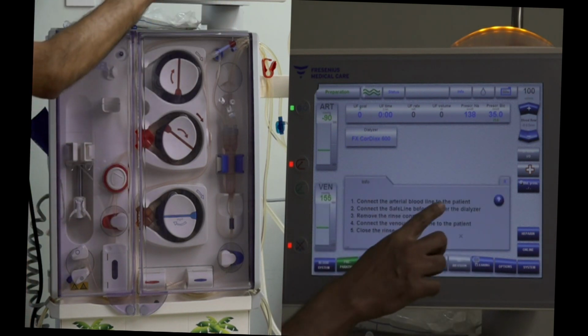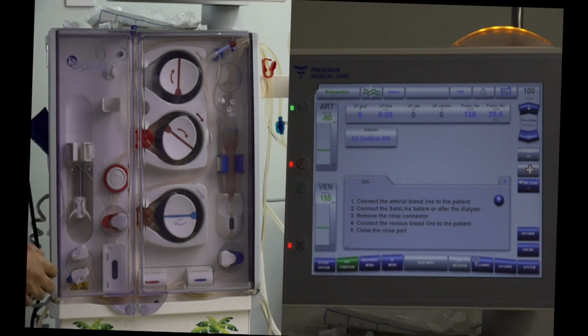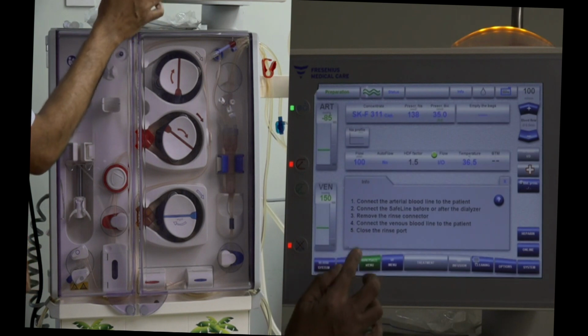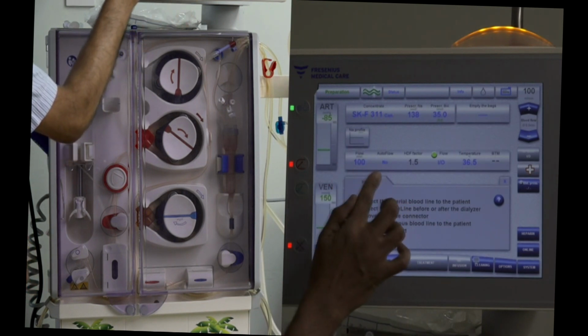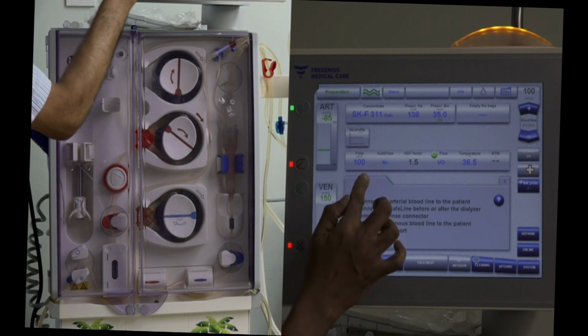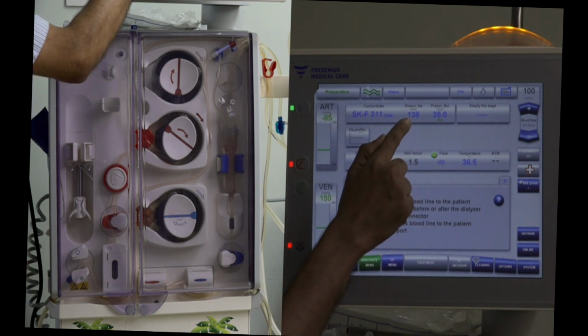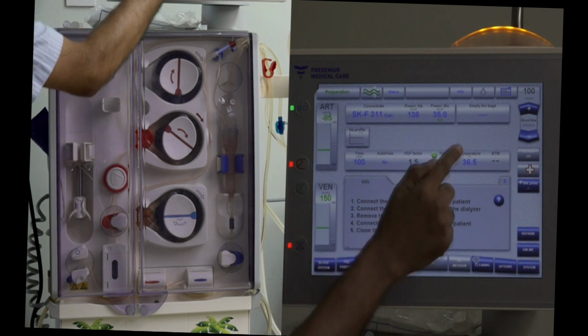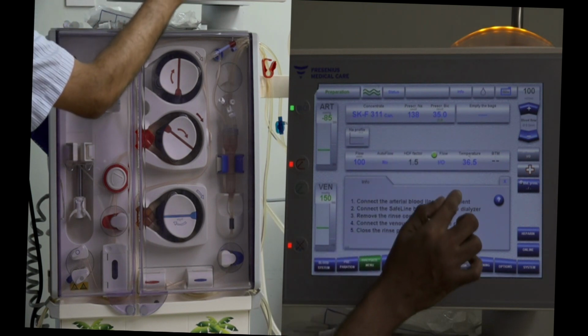The machine is telling us to connect the arterial line to the patient, the SafeLine before or after, as to the ports which I showed you earlier on the tubing, depending on whether we want to deliver pre or post substitution fluid, and the venous line also to the patient. Before we connect the patient, however, let's look at the settings on our machine. In the dialysate menu, we said earlier that we would be choosing a flow of 100 ml per minute. We have a dialysate sodium of 138, a bicarbonate of 35, and a temperature at 36.5.